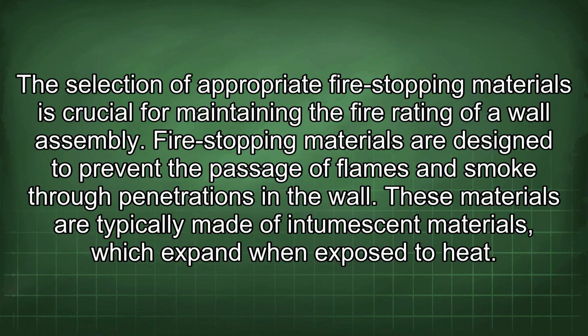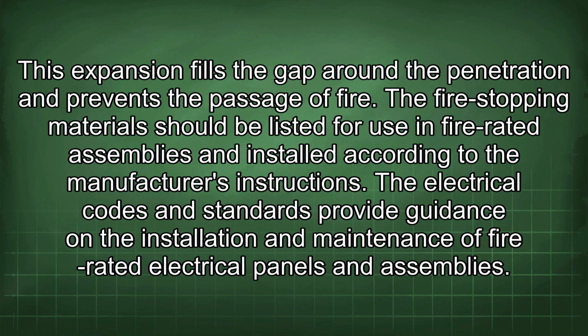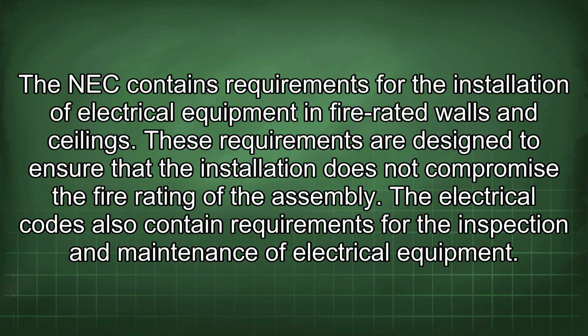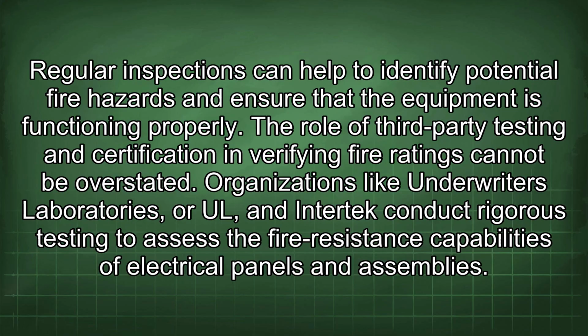Fire-stopping materials are designed to prevent the passage of flames and smoke through penetrations in the wall. These materials are typically made of intumescent materials, which expand when exposed to heat. This expansion fills the gap around the penetration and prevents the passage of fire. The fire-stopping materials should be listed for use in fire-rated assemblies and installed according to the manufacturer's instructions. The electrical codes and standards provide guidance on the installation and maintenance of fire-rated electrical panels and assemblies. The NEC contains requirements for the installation of electrical equipment in fire-rated walls and ceilings. These requirements are designed to ensure that the installation does not compromise the fire rating of the assembly. The electrical codes also contain requirements for the inspection and maintenance of electrical equipment. Regular inspections can help to identify potential fire hazards and ensure that the equipment is functioning properly.